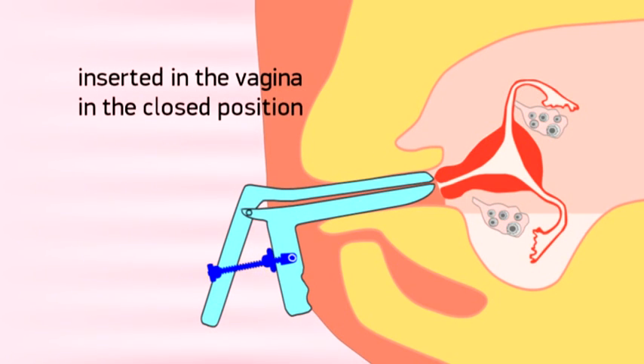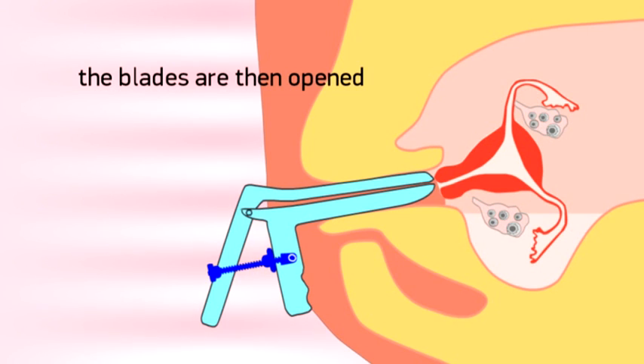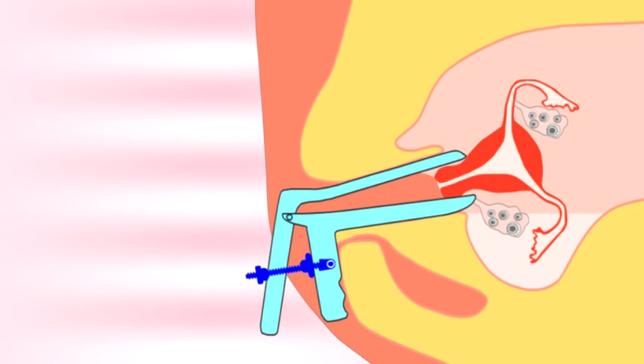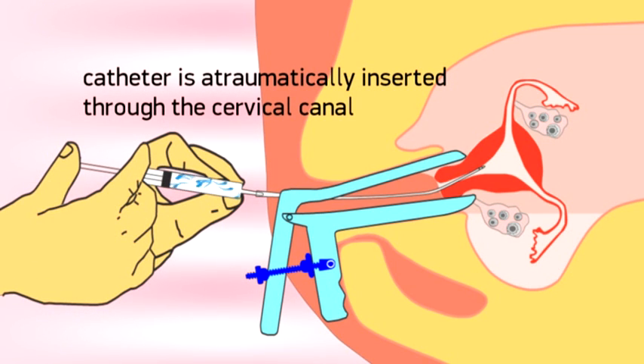The Procedure. The DNB Cervical Clamp is inserted in the vagina in the closed position, with the inner nut being close to the posterior blade handle. The blades of the DNB Cervical Clamp are then opened by turning the outer nut clockwise, thereby allowing good visibility of the cervix. Next, the insemination catheter is atraumatically inserted through the cervical canal into the upper part of the uterine cavity.